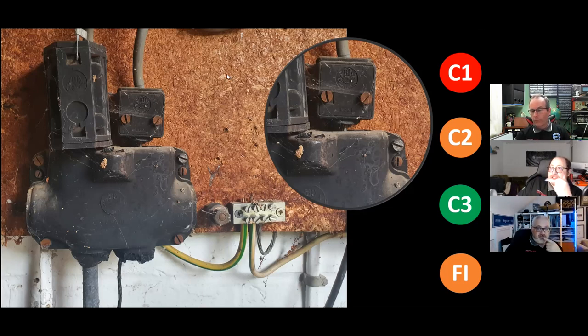I do. I think training on that equipment should be part and parcel of our ongoing CPD. I think it's definitely exposure to a live conductor. You can't ignore that, and if you say it as simply as that, then you're going to have to go, well, that must be a C2 at least, maybe a C1. What has the survey said? We're hovering around C1s and C2s.